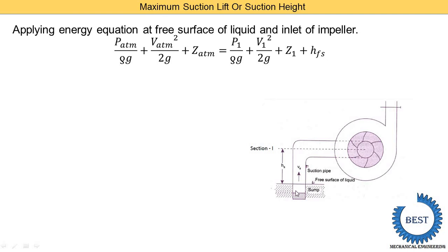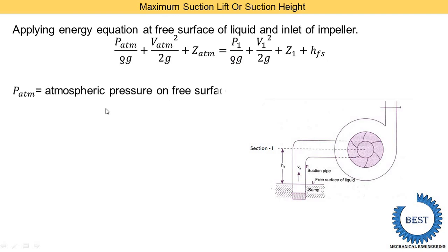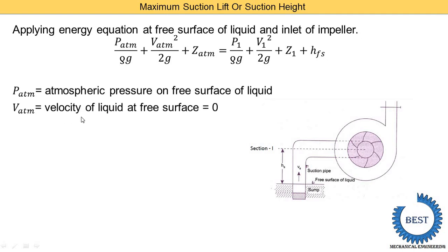When water is supplied from the sump to the impeller through the pipe, there are friction losses. So energy is reduced at the inlet of the impeller, and we add this loss term hfs. Now, v_atmosphere is the velocity of the liquid at the free surface of the sump — since the water is stationary in the sump, v_atmosphere is considered zero, so that term is zero.